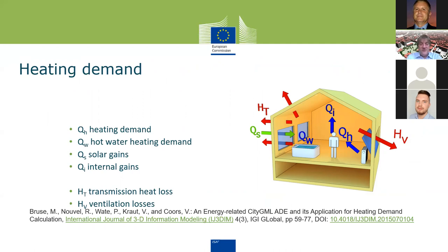And that's why we developed this tool called Simstadt, where we calculate heating demand by taking into account solar gains, internal gains, heat loss through transmission, ventilation losses, and not only heating, but also hot water demand, or heating for hot water in that sense.